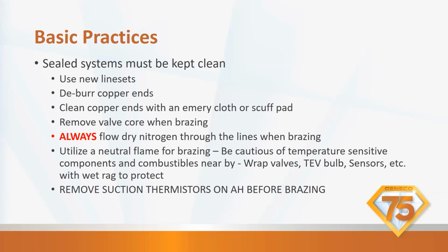You're going to be able to pump it down, and every time that we pump it down, we're going to pump down by micron level, not by time. So throw your micron gauge on, pump it down. As soon as you get down to where it needs to be, shut it off, make sure it doesn't rise, and off you go. Okay. You can do this very quickly if you're careful how you treat your line sets.